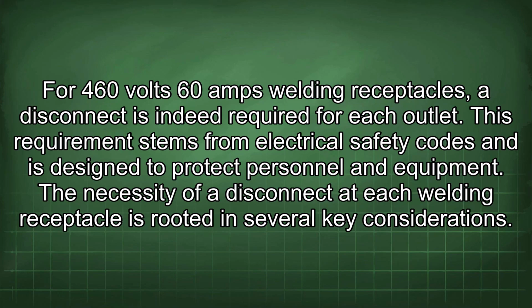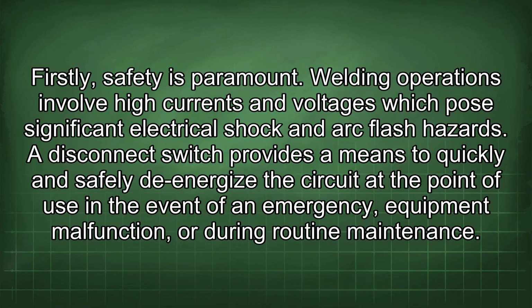For 460 volts 60 amps welding receptacles, a disconnect is indeed required for each outlet. This requirement stems from electrical safety codes and is designed to protect personnel and equipment. The necessity of a disconnect at each welding receptacle is rooted in several key considerations. Firstly, safety is paramount. Welding operations involve high currents and voltages which pose significant electrical shock and arc flash hazards.